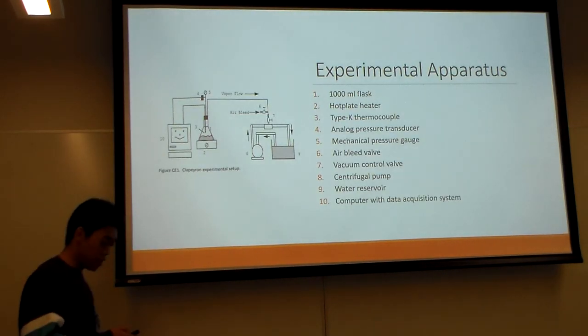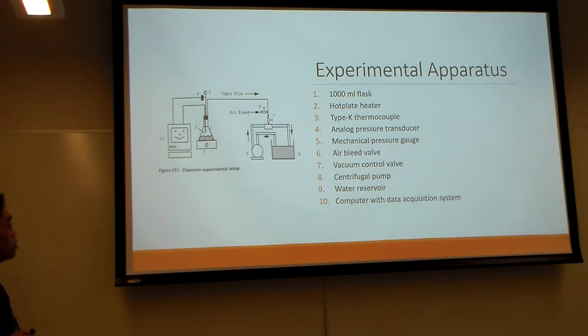Yes, as we can see here, number 3 is the thermocouple, and this one is water. The thermocouple needs to be placed submerged in the water, so that it will measure exactly the condition of the water instead of the temperature of the flask or the glass beads.